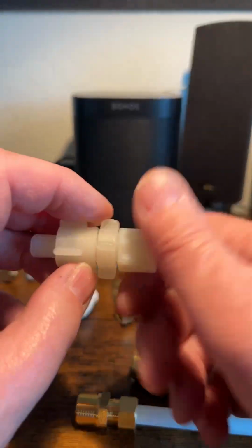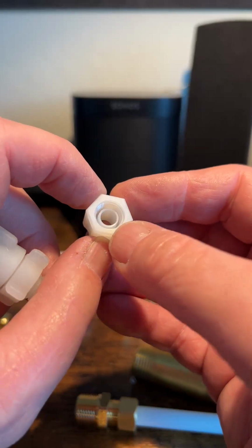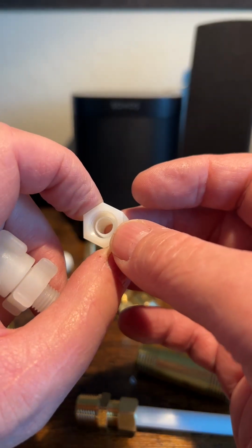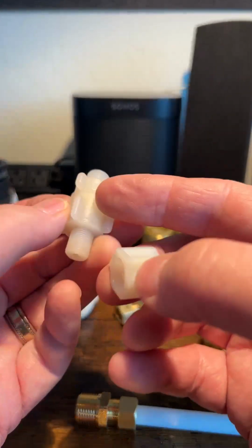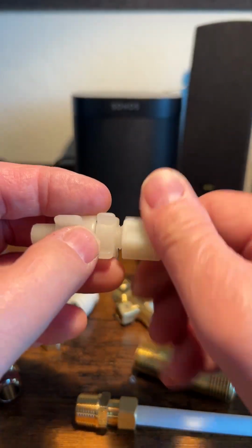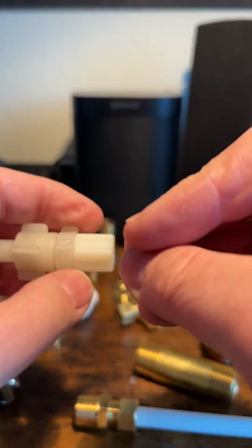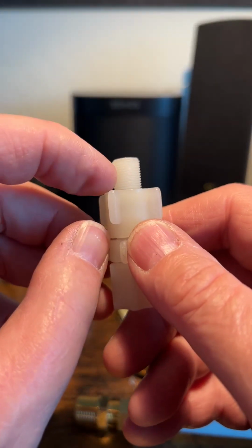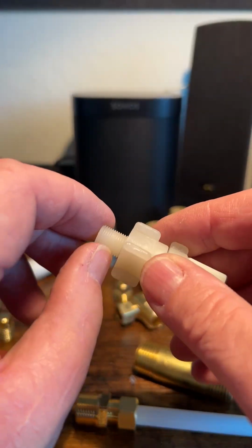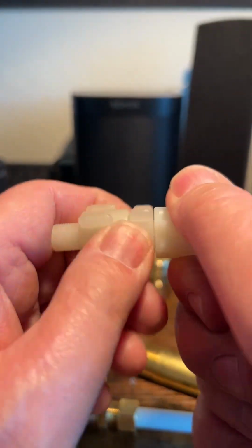Another type is there's plastic ones too. So this manufacturer kind of welds that ferrule inside there. You see that? So this is for your 1/4-inch chemical tube on a dish machine. This is a check valve inside here, but this is a compression fitting, and it'll compress down that tubing so it won't leak, right? And this is a pipe thread. It kind of looks like a compression thread, doesn't it? But the smaller these pipe sizes get, the more confusing it looks. It kind of looks like a compression thread, but it's just not.